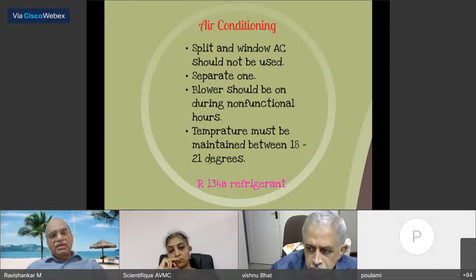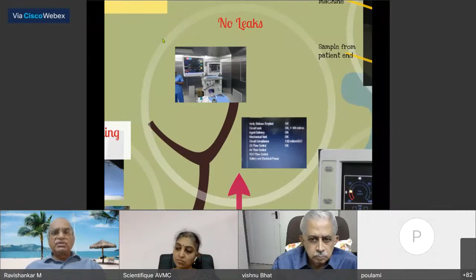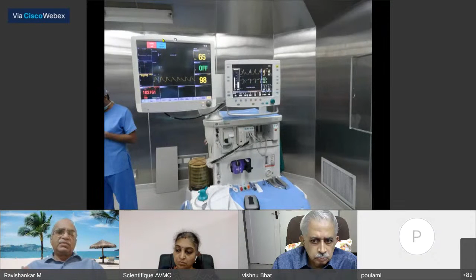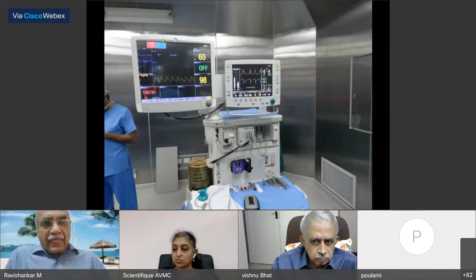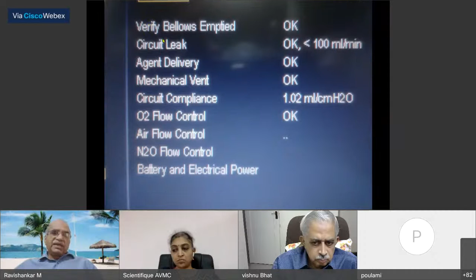Coming to anesthesia machines, what is important about the anesthesia machines? Inside the theater, we do not want the machines to pollute the atmosphere. So the first and foremost thing is to avoid any leaks in the circuit. You now have these enhanced, advanced workstations, which are quite sophisticated, and they do a leak check at the beginning to make sure that the leak is less than 100 ml per minute.